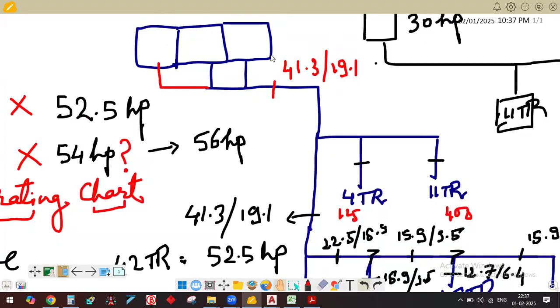It is very necessary that this pipe size and this pipe size match. Suppose here I am getting 34 and here I am getting 41, it means my design is wrong. So both should match, or the pipe size you select from this table should always be on the higher side. And this is the configuration. Suppose I am selecting 54 HP, so I am going with 18 plus 18 plus 18 HP.